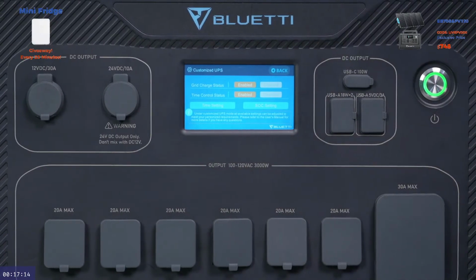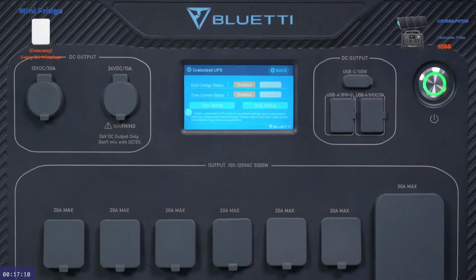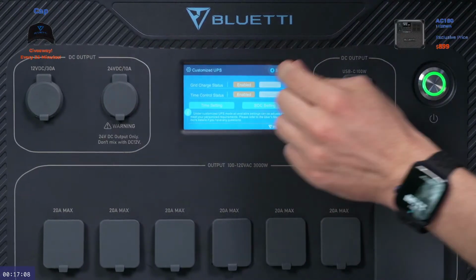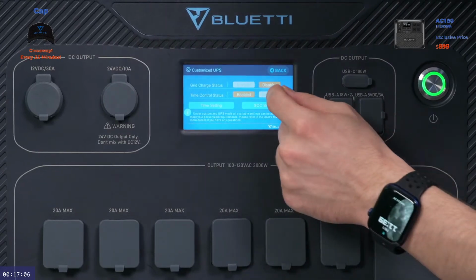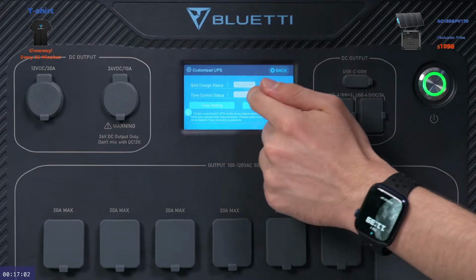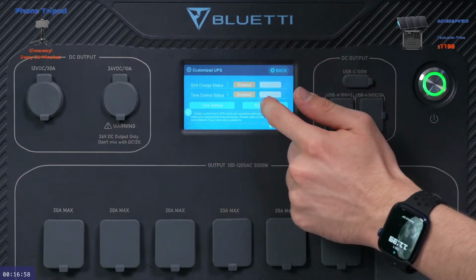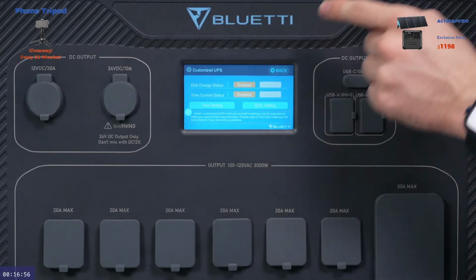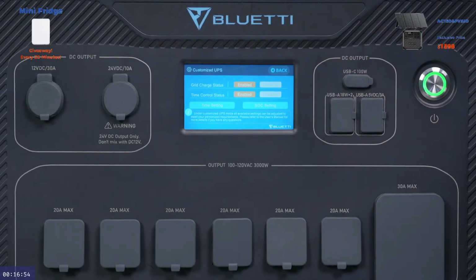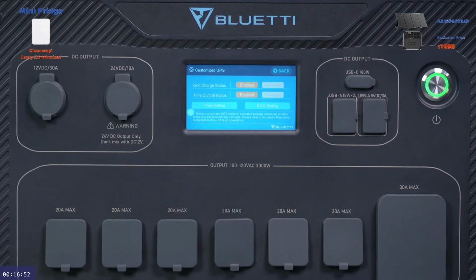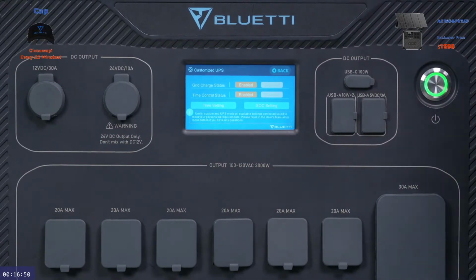Customize UPS, as the name implies, has grid charge status enabled or disabled, and time control status enabled or disabled. First enable them, and then you can control time settings and SOC settings. This is my favorite mode - you can adjust not only the time, but also the SOC settings.